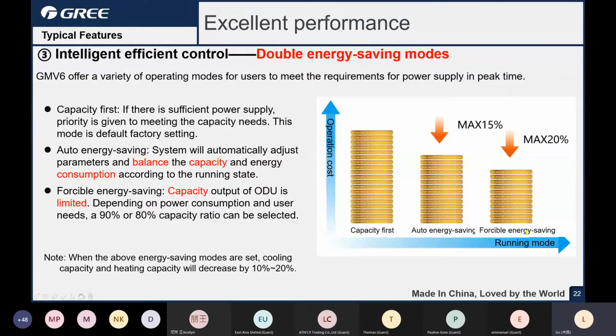Next one is the forcible energy saving. That means if you set this energy saving, the unit will limit the frequency of the fan and the compressor to reduce the power consumption. And the maximum you can get is about 20% reduction in power consumption. Okay, that's the energy saving function. But just remember that no matter whether you choose the auto energy saving or forcible energy saving, absolutely the capacity will be affected, about 10 to 20%. Okay, and you can choose the setting according to your demand.